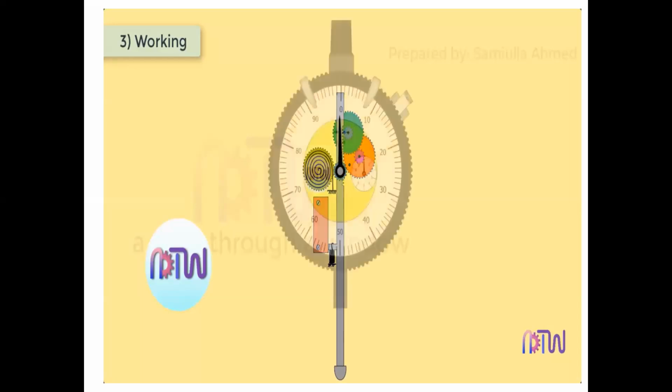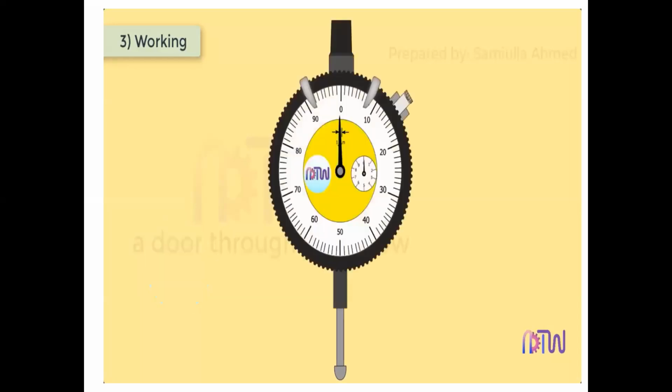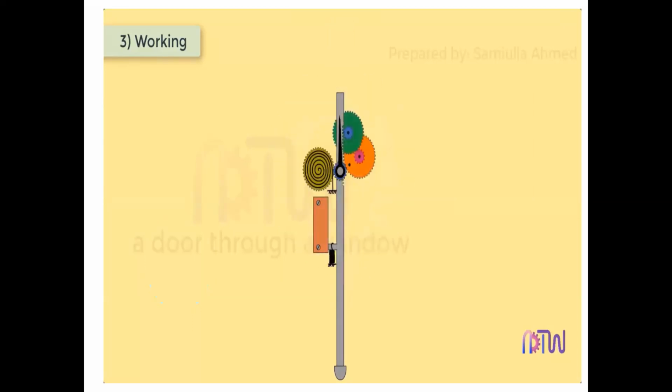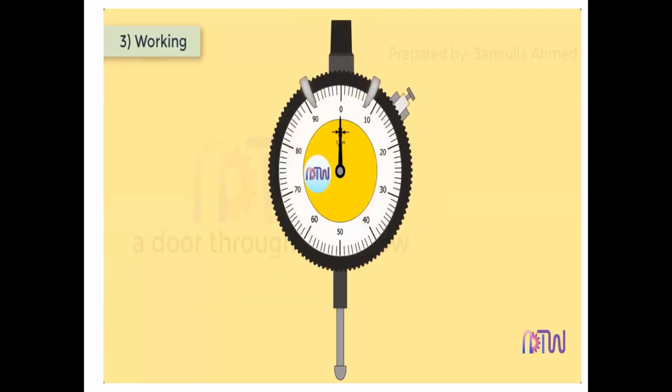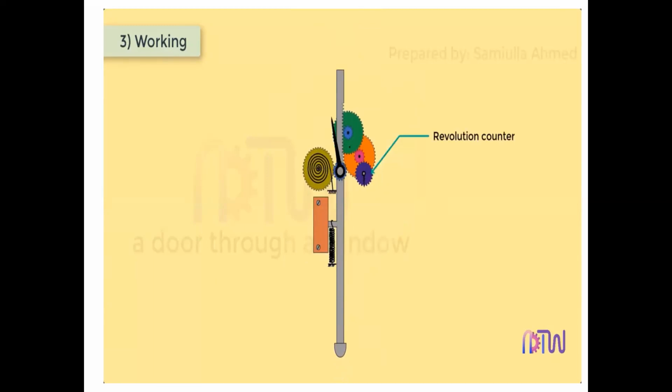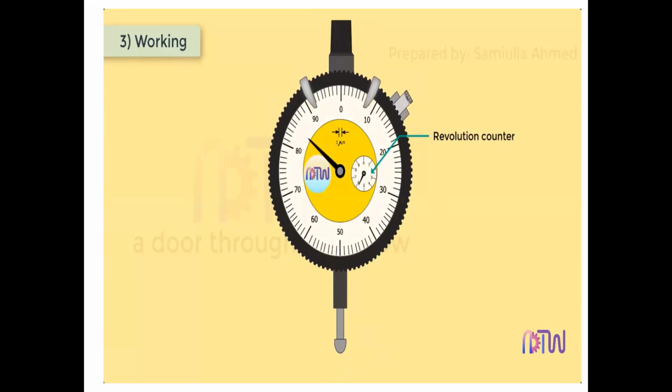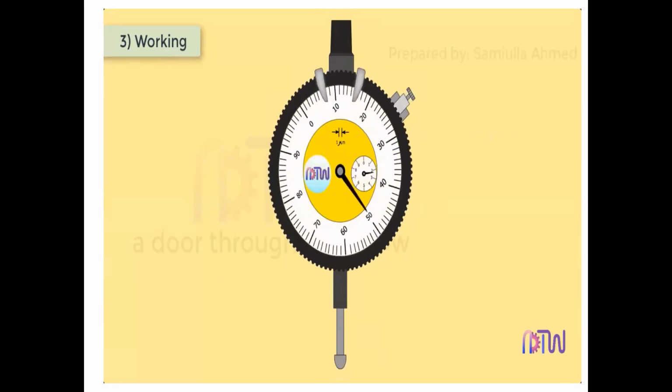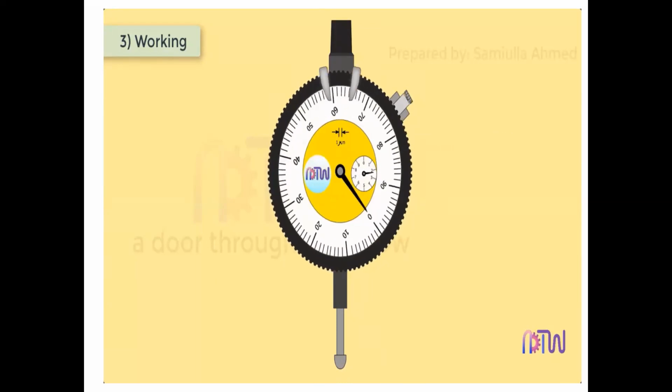After final assembly, each dial gauge is thoroughly tested and checked and properly calibrated either by a calibrated micrometer head or by the use of slip gauges. If the pointer moves more than one revolution, a revolution counter is also incorporated, which will correctly indicate the number of revolutions made by the main pointer, and thus enable a complete reading to be made when the gauge is used for direct measurement. Also, we can rotate the round graduated scale to set the pointer to 0. In some dial indicators, 2 range pointers are given on the bezel, which are used to set the range.